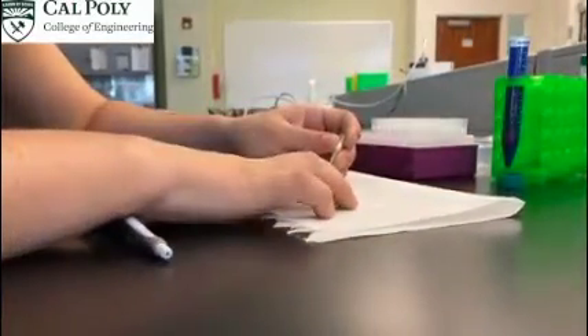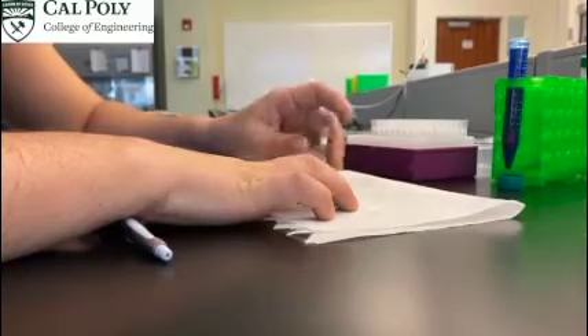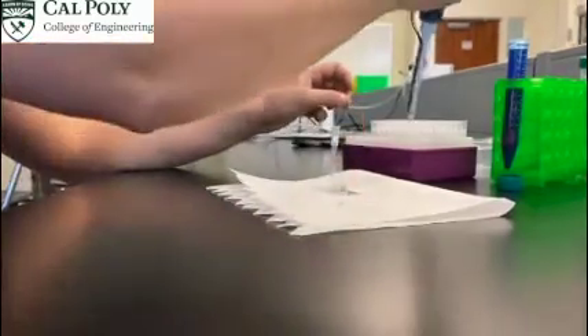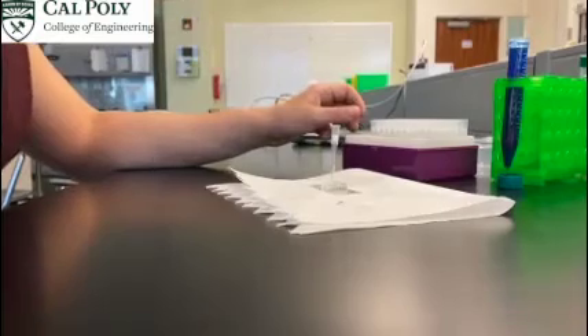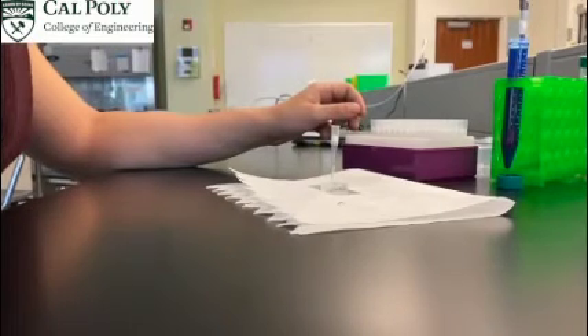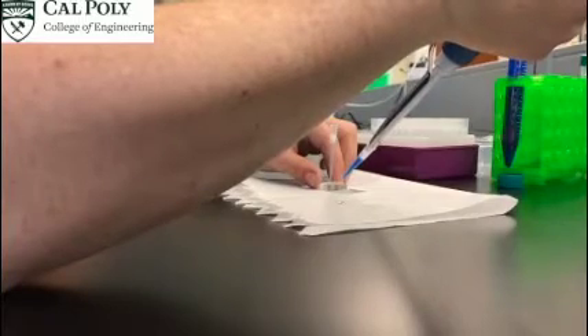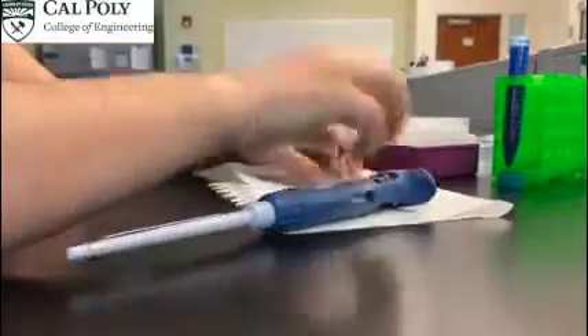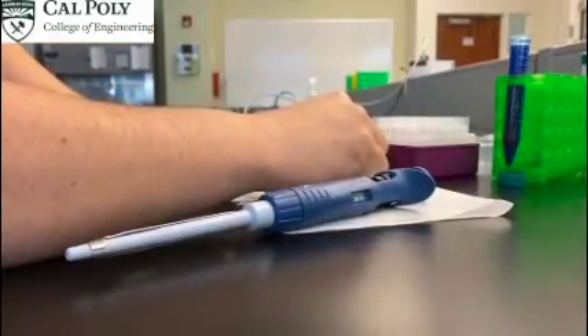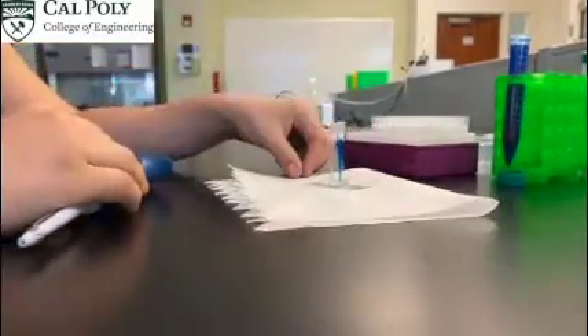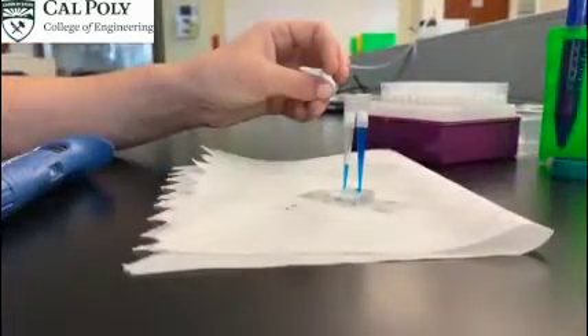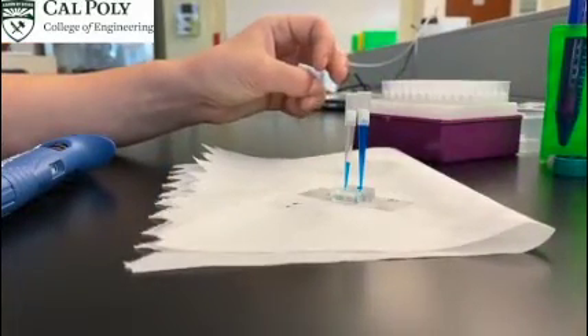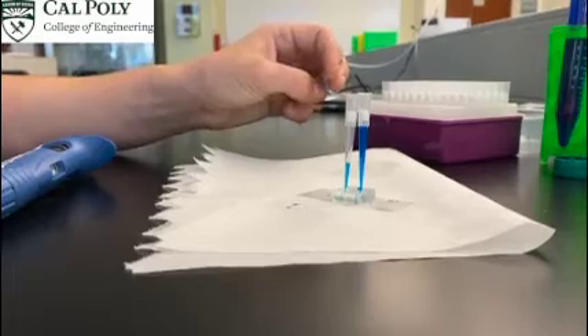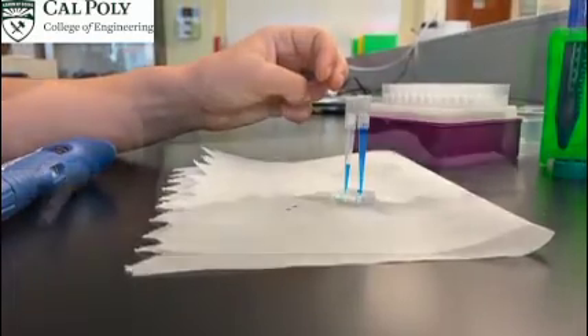Passive loading of the devices involves placing an empty 200 microliter pipette tip into the outlet of the device and loading 200 microliters of cell solution, or in this case, colored water, into the pipette tip that will be inserted into the inlet of the device. Without depressing the plunger at all, I eject the tip filled with solution into the device, leaving it behind to flow on its own. The pressure head height formed by the media solution will cause the solution to flow into the device through the chamber until both tips are at an equal media head height.